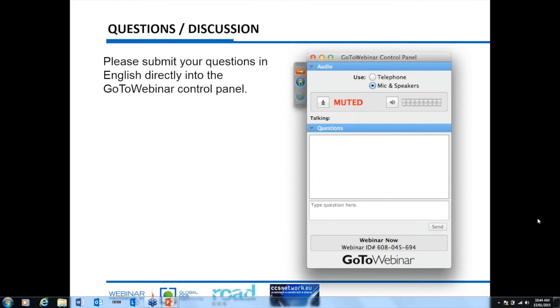Okay, thank you. Andy, based on your experiences of going through the design process on road, would you have any recommendations for the capture readiness of a power plant in regards to water systems as people look to design and construct capture-ready power plants? Well, I think it's worth being aware of the increase in water consumption and making sure that additional cooling is available for the full carbon capture. Capture readiness is a difficult one because the cooling water load and well, all the tie-in points tend to depend on the specifics of the capture technology selected, and therefore it's difficult to do a design that's optimised for a future technology if you don't know exactly what the future technology is.